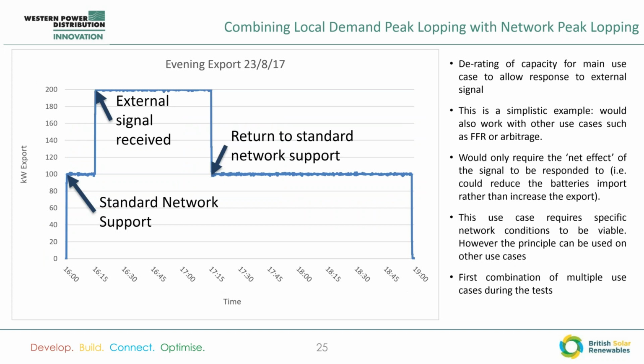So this is the first combination of 2 methods as well. We're operating 2 things at the same time, the standard network support and the external signal received. It would also work, as I say, with other use cases, depending on what the exact limits were on what the battery could do while it was providing this additional support. It does require specific network conditions to be useful. So the system has to be close to capacity and someone wants to have an increase in load. And that's when this use case can come into its own.